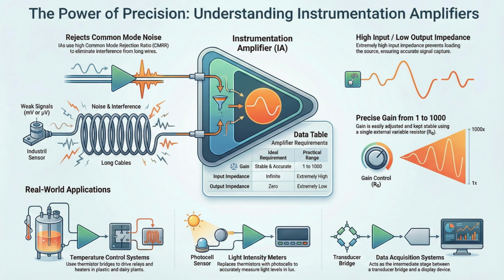And why is that specific number so critical to you? Because of linearity. If I am calibrating a medical device or a scientific instrument, I need a linear relationship between the photon hitting the sensor and the number on the screen. The stable and accurate requirement ensures that the internal components of the IA don't drift with temperature.